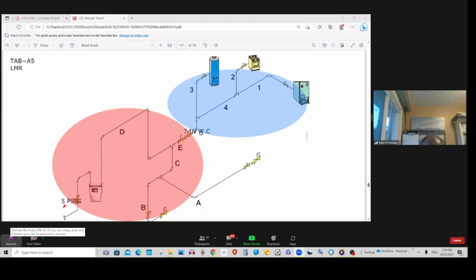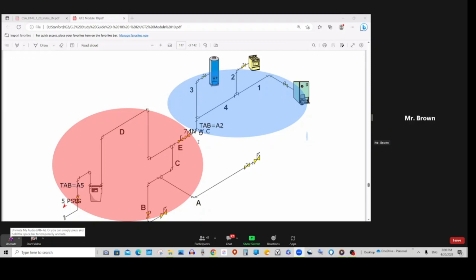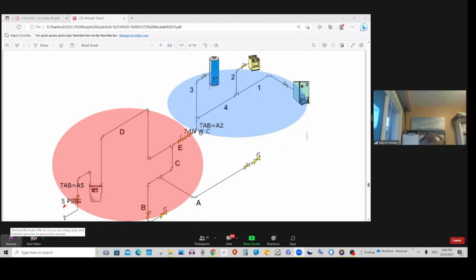Okay? If you remember, at the beginning I said that for pressure less than 2 psi on those tables, all the fitting is included. It's 7-inch water column. So what does it mean? It means all the fitting is included. When a question like this comes, with 2, 3, 4 of them, it doesn't matter.